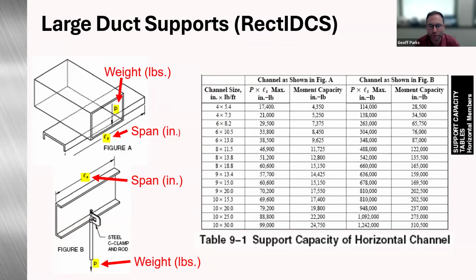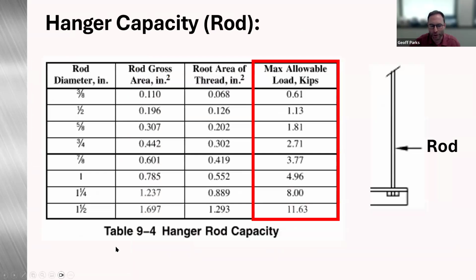Also in the rectangular industrial, table 9-1 has the same chart, although this is for horizontal channel, and it's either in the figure A dimension, flat, or B dimension, standing up. So you can size your channel and angle as well. And then also out of the rectangular industrial table 9-4, this is your hanger rod capacity. So this is giving you your rod diameter and the capacity of that rod, which is based in kips. So you would multiply by 1,000, so that would be a 610 pound load on that for a 3/8 diameter, where a ½ inch rod would be 1,130 pounds.